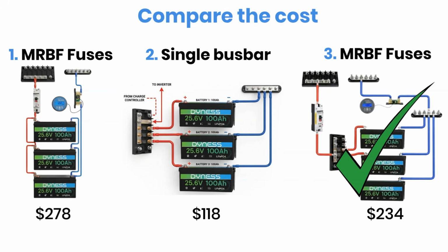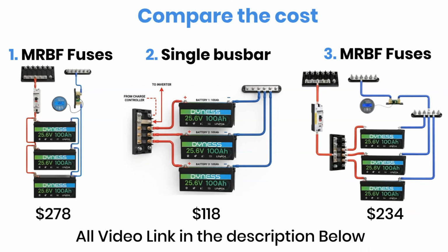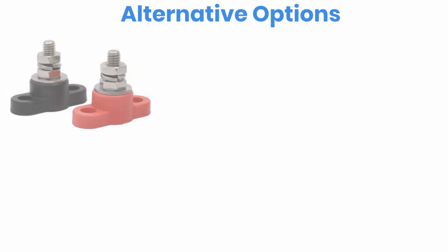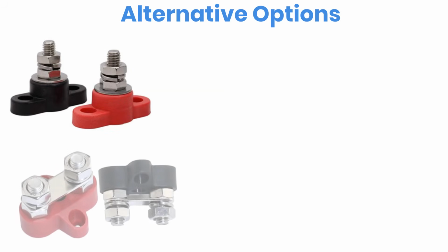One thing I haven't covered in detail here is cable sizing and fuse selection. Those topics depend on factors like cable length, maximum current, voltage drop, and the equipment you're using. They're important enough to deserve their own dedicated discussion rather than trying to squeeze everything into one video. Before we wrap up, here are a few extra tips that can make your installation even better. If you're only connecting 2 batteries with MRBF fuses, compact single-stud or double-stud busbars can reduce both cost and wiring clutter while keeping the installation neat.